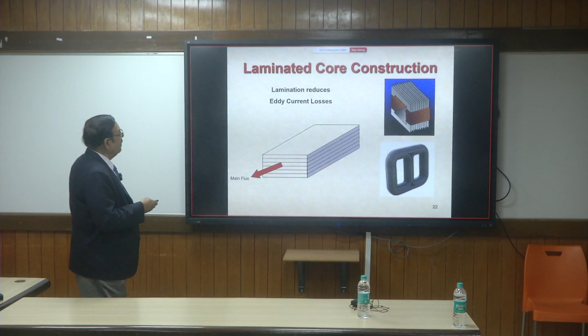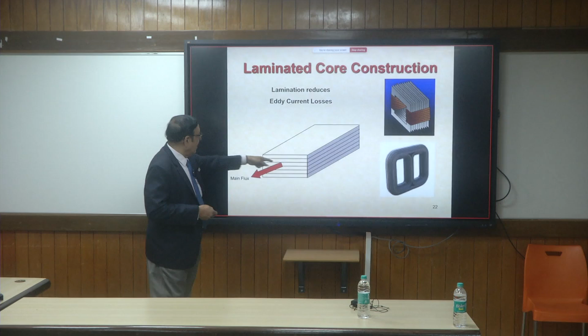Okay, we have laminations basically to reduce the eddy current, and in laminated core construction, the flux is in this direction, so you have laminations like this. Shell type transformers is one particular type of construction, because you have a middle limb and you have the coil inner and outer, and I don't want to mention which is primary, secondary, that depends on your application, and you have the yoke going around. Because the flux is assumed to split equally in both directions, the size of the core on either side can have a width which is 50% of the middle limb.